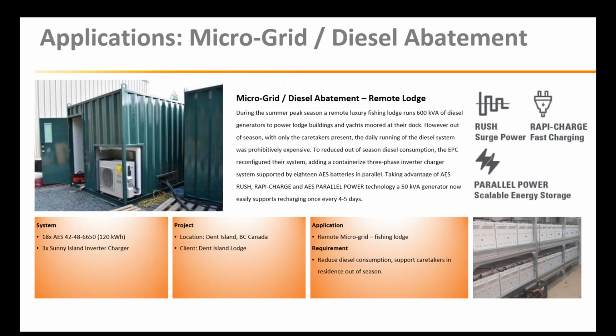So they undertook a project where they installed the battery bank and a much, much smaller generator to charge that battery bank, and overall massively reduced the amount of diesel fuel that they were consuming. In this case, the savings paid for the batteries and the inverter and small generator within 1 season. Going through their second season, they're looking to save enough money to actually add solar to the overall system and begin removing some of the need for that 600 kVA diesel genset in the beginning. So there's a lot of interesting things that can be done when we start combining diesel and solar with the use of sophisticated batteries, etc.